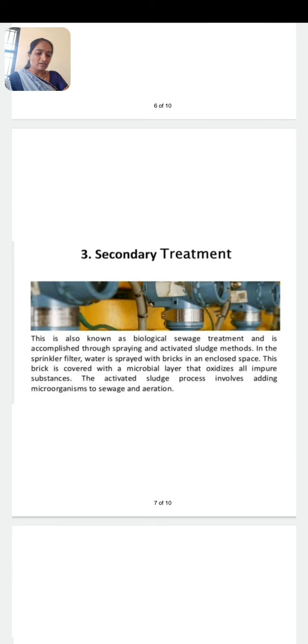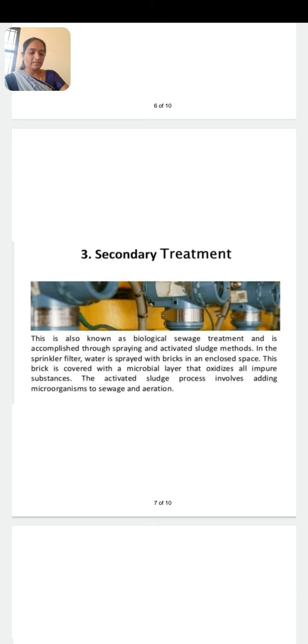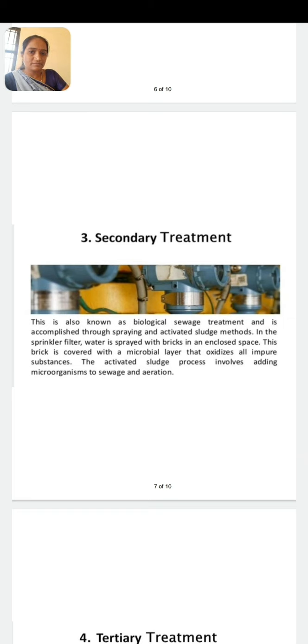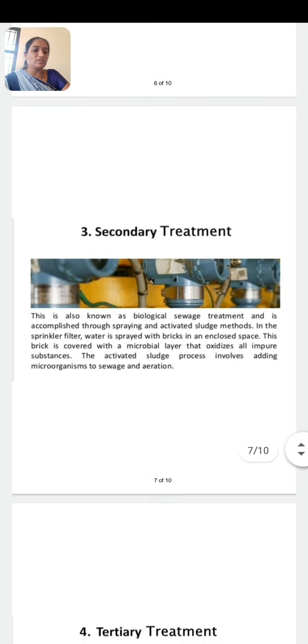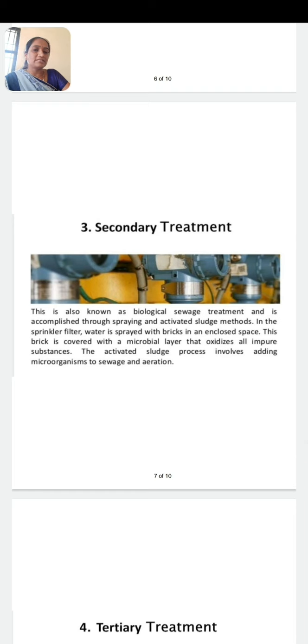In secondary treatment, the primary effluent which floats above is agitated constantly and mechanically, and air is pumped into it. The aerobic bacteria grow vigorously and form floc masses, held together by slime and fungal hyphae to form mesh-like masses. These aerobic microorganisms consume the major part of the organic matter present in the effluent. Due to this, the biological oxygen demand, or BOD, is significantly reduced.